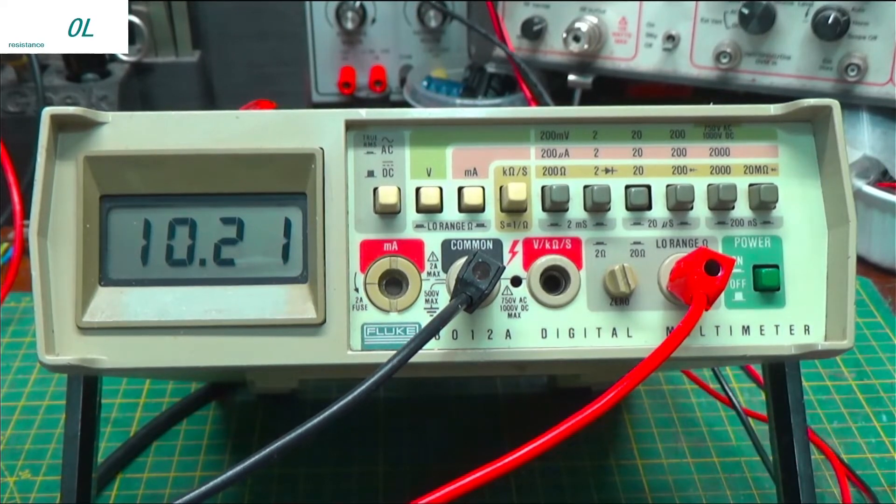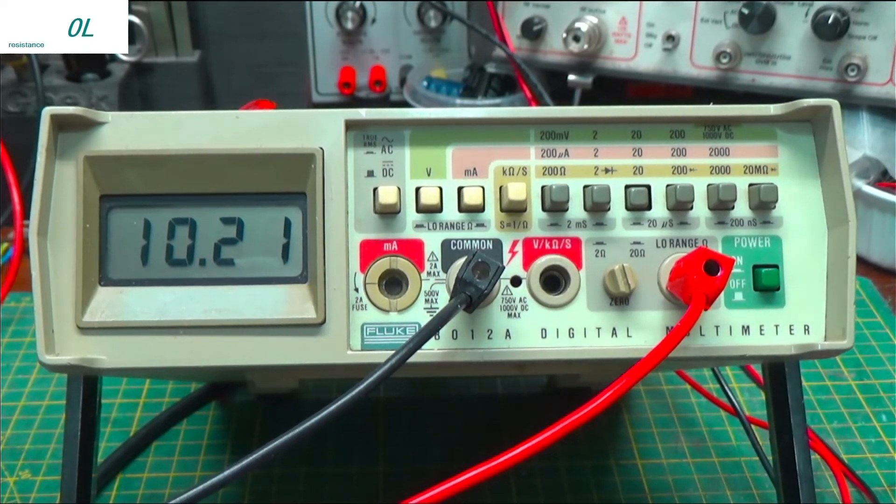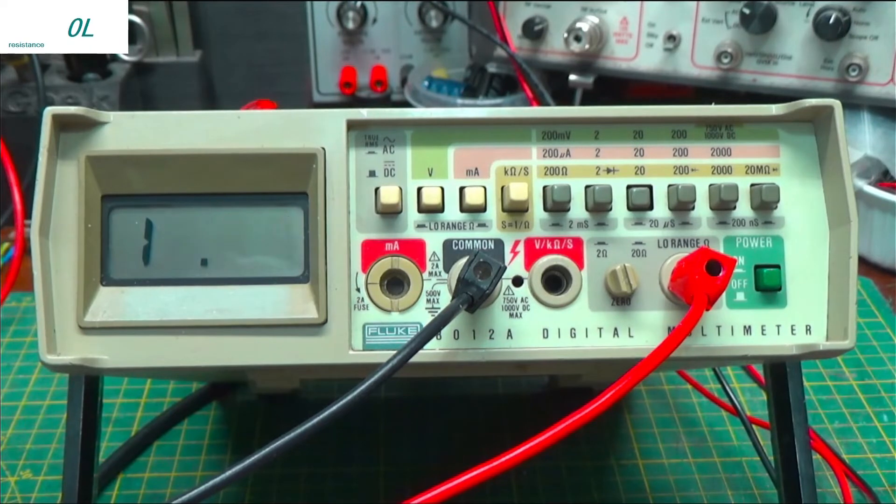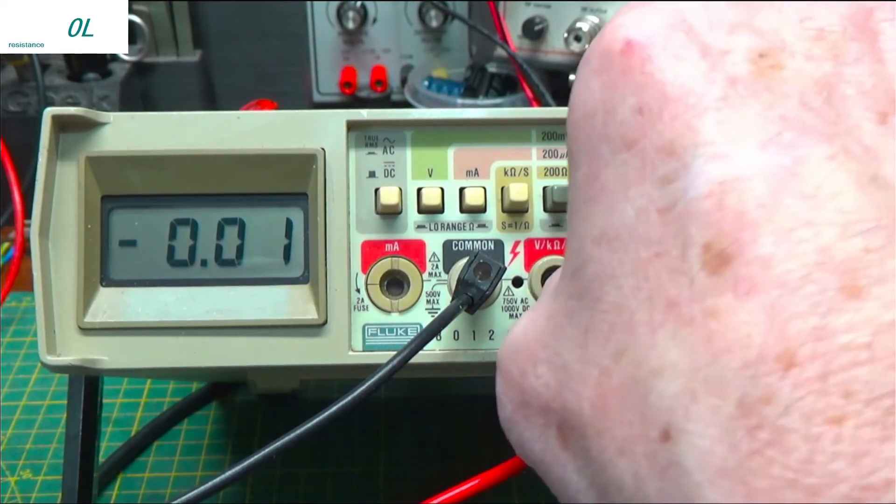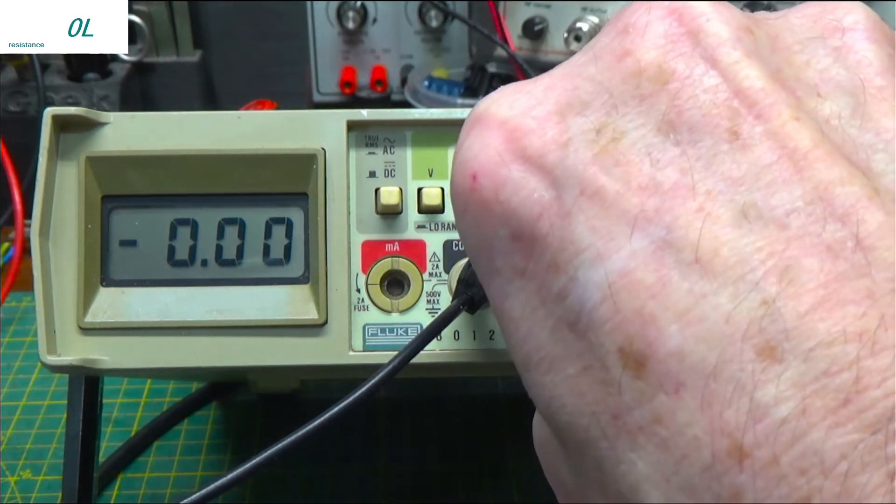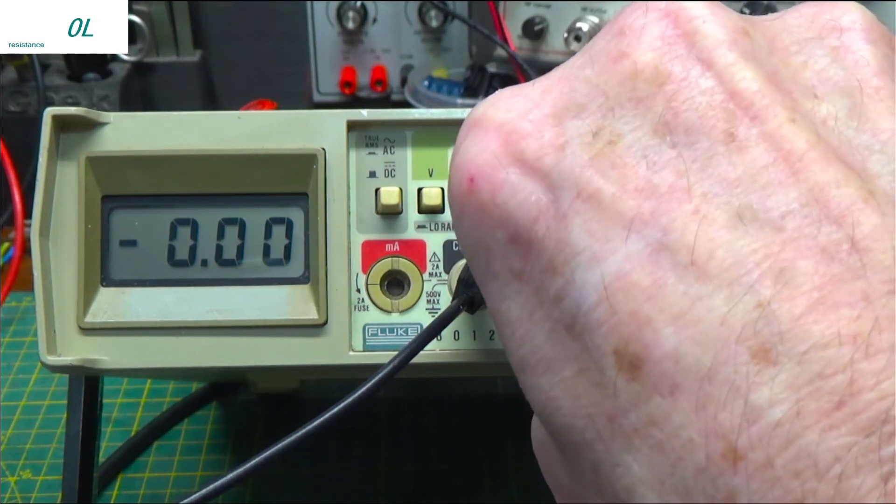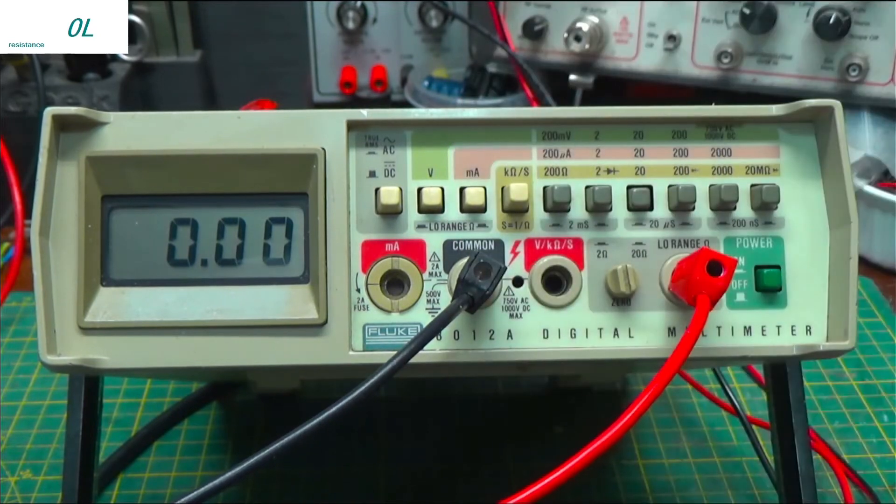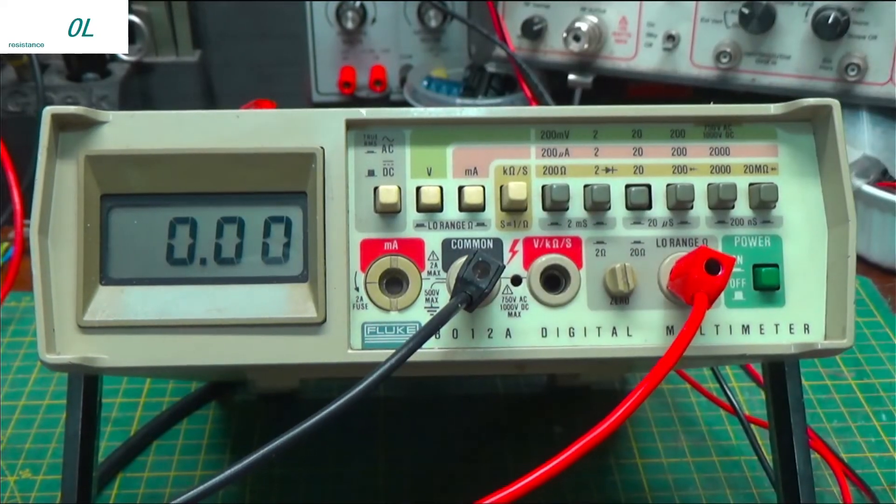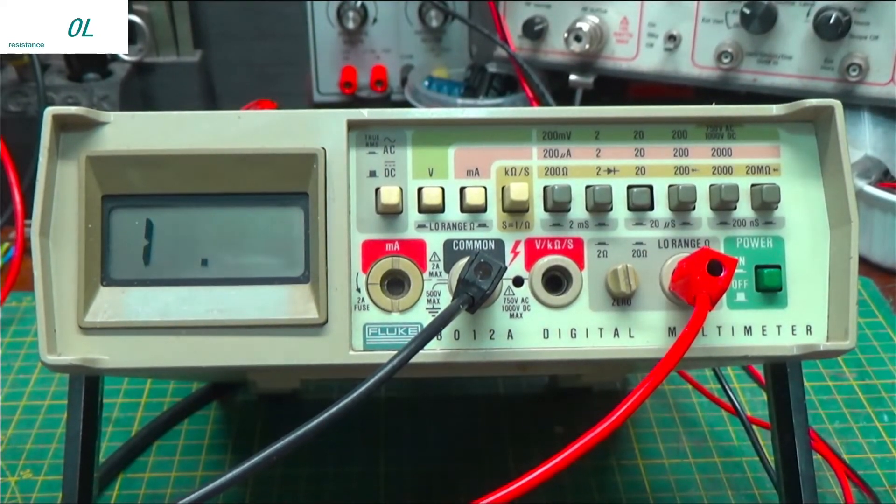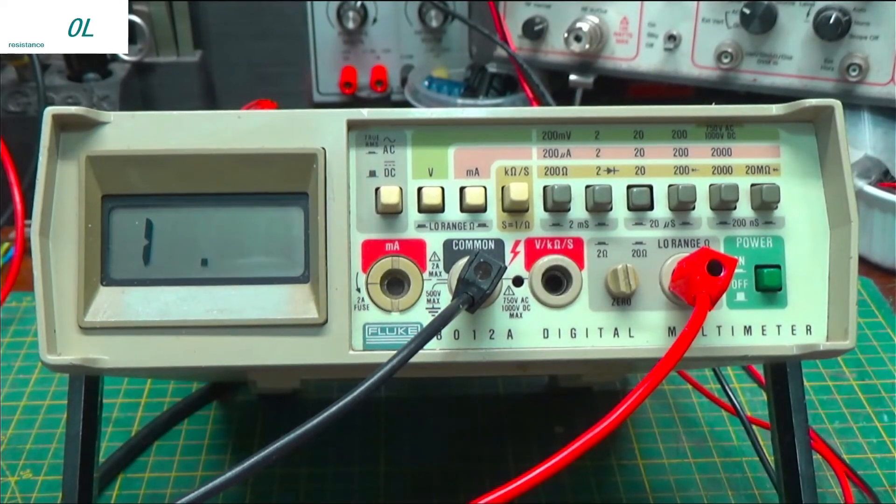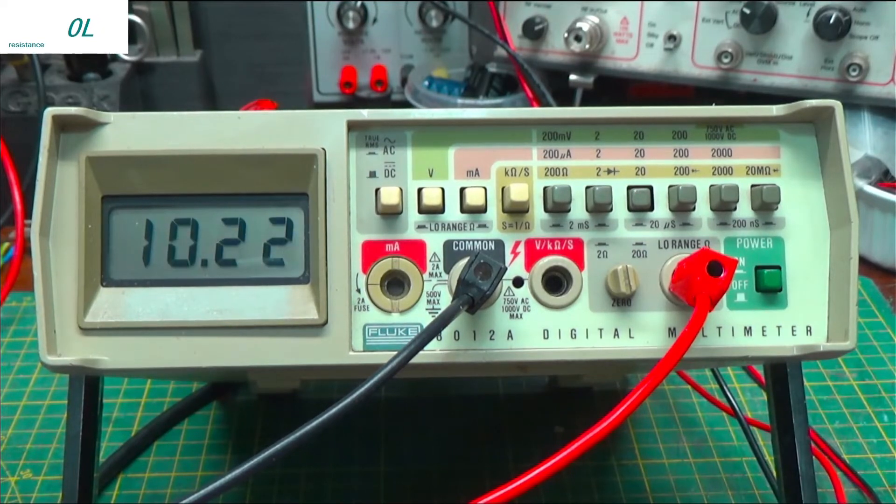However, in order to read this correctly, what you do is you short your leads together. You adjust this little pot right there for dead on zero. And then measure your resistor. 10.22.